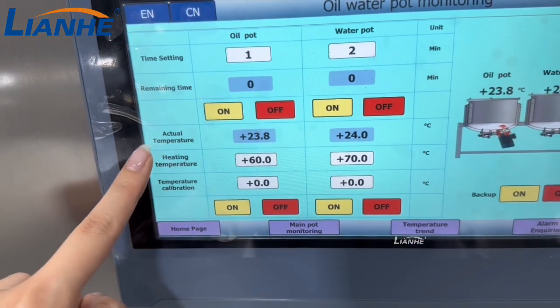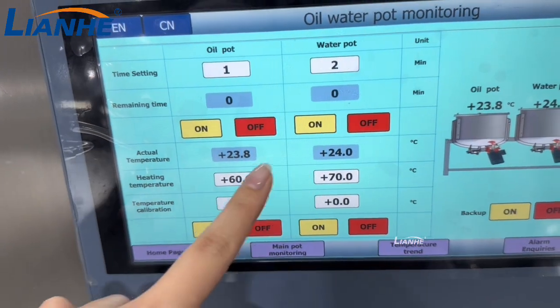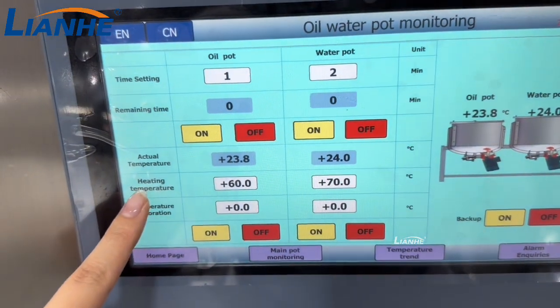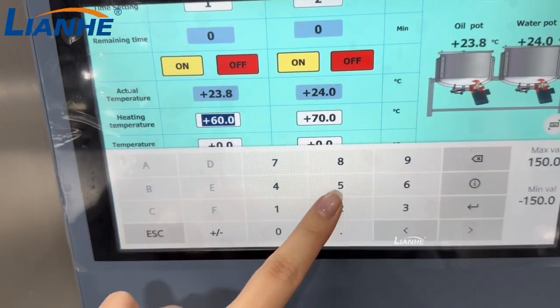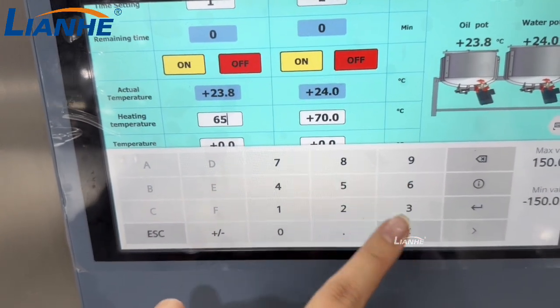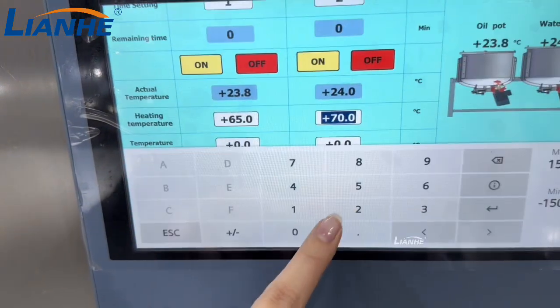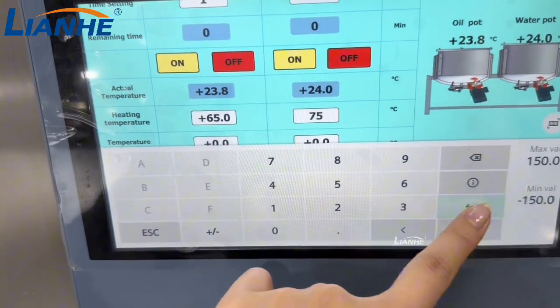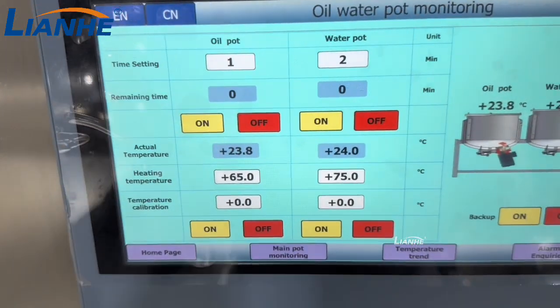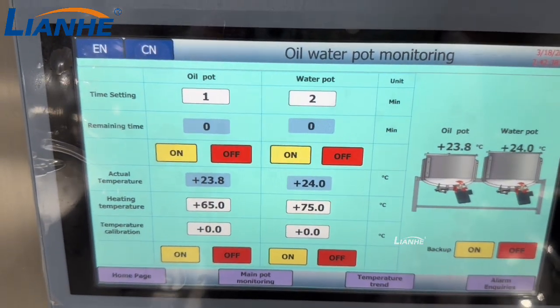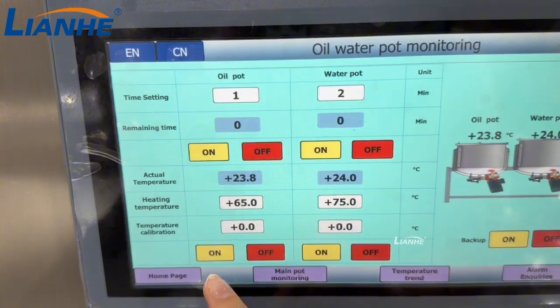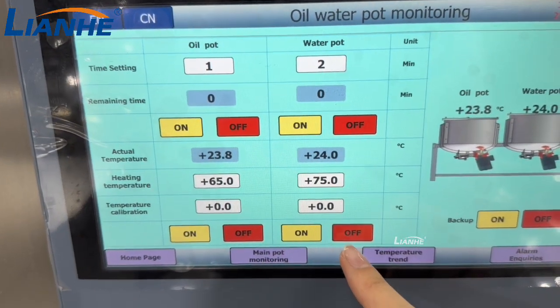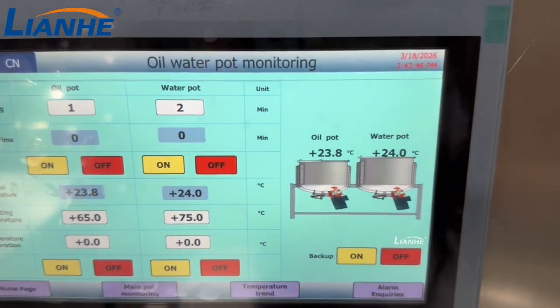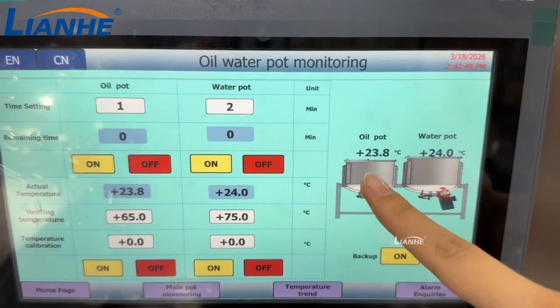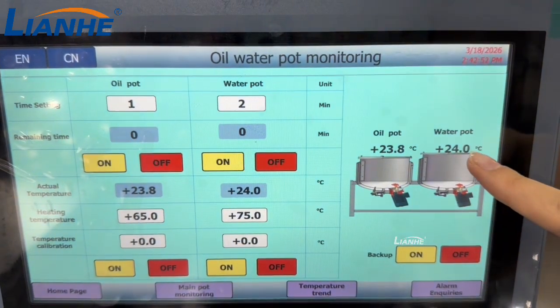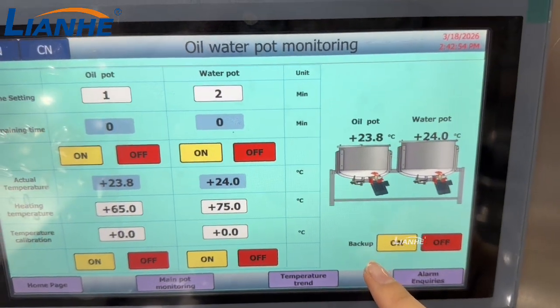Here we display the actual temperature for the oil pots and water pots, and then you can set the temperature like here for the oil pots, like 65 for reference, water pots like 75 for reference, and then this is the temperature calibration to adjust the temperature just like the main tank, and then this is the turn on and turn off function of the oil pots and water pots, and you can see the diagram from here have the actual temperature display here. Then this is the backup use function.